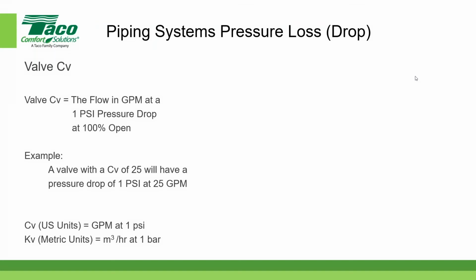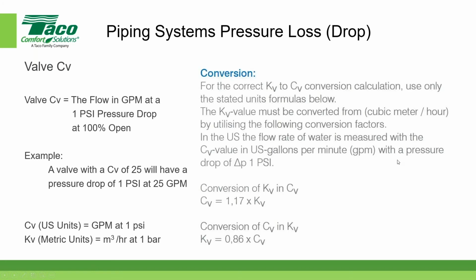So one last thing I want to show you on this slide is that I'm using inch-pound units. In the metric system it would be cubic meters per hour at 1 bar. That is called the kV, and the conversion is this little table here. So if you're converting from CV, which is in inch-pound units, to kV, the kV would be equal to 0.86 times the CV. And if you wanted to find the CV and you were given the kV, you'd multiply by 1.17 to get the CV. So that's just the conversion between those two.